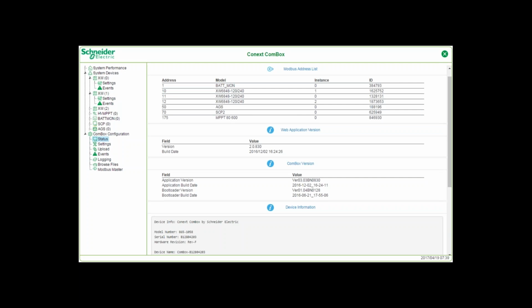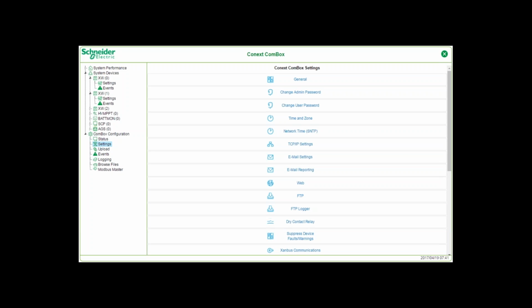The ComBox status screen shows all the Xanbus devices with their unique ID and Modbus address. Also listed is the ComBox version, which tells you if you have the latest ComBox firmware. Here we see the settings for the ComBox. Time and zone can be entered manually or display network time with an internet connection. TCP/IP settings allow setting up a static IP for port forwarding through a VPN router. Email setup allows for production reports and fault status to be sent to select individuals. Also file transfer protocol setup and dry relay contact setup.